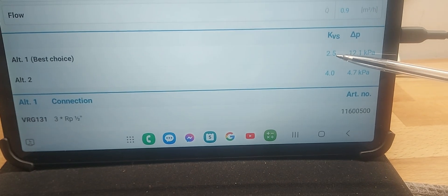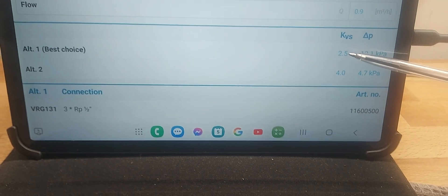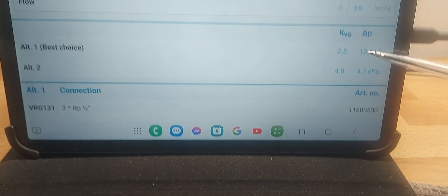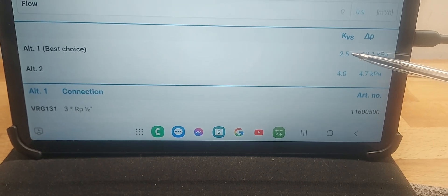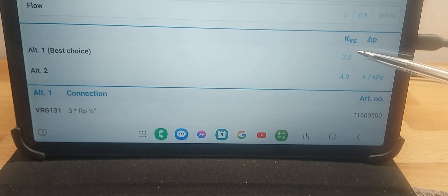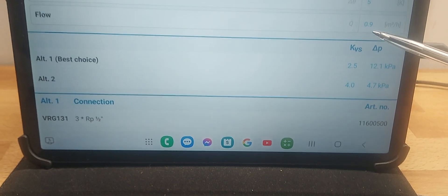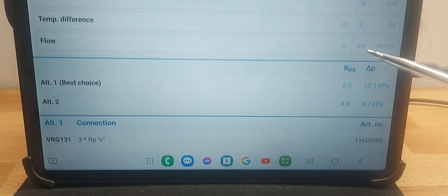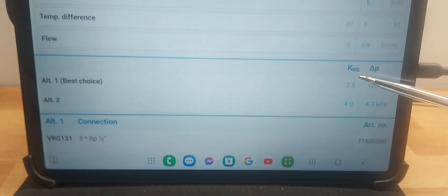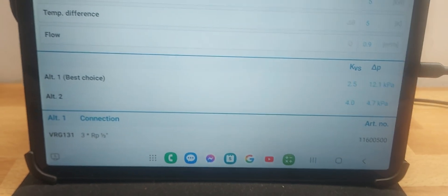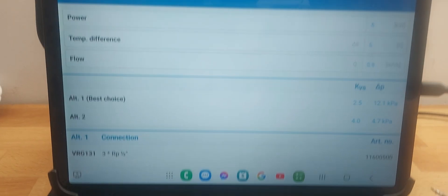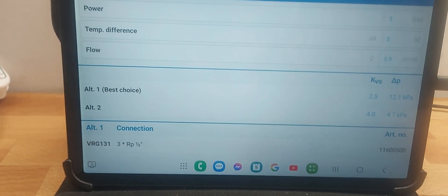The maths behind this is that the valve should provide the same pressure drop through the valve at that flow rate. I haven't done the calculations to prove that's how this app works, but that's how the maths works when you learn it from the theory papers. I've been using this app to size my ESBE valves and I've been having good success with it. I have done another video on the mathematics behind it, but this is the easy way to do it.